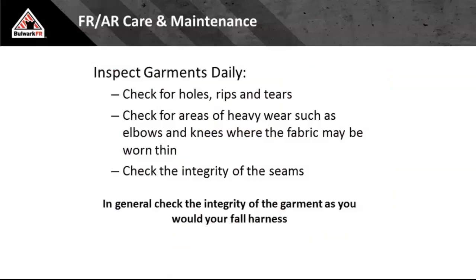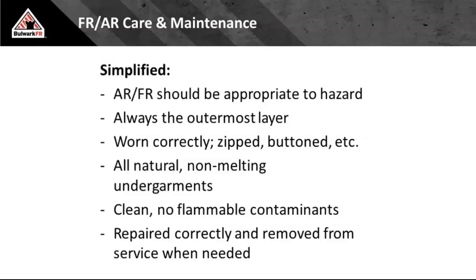So inspect your garments daily. Check for holes, rips, and tears. Check areas of heavy wear such as elbows, knees, where the fabric may be worn thin, and the integrity of the seams. Take the same mindset with your FR, AR clothing that you do with your fall protection. Take the same attitude you would with your hard hat. You don't allow hard hats with cracks and chips to go into service. You don't wear cracked, chipped safety glasses. You don't wear just one hearing protection because the other side's all messed up, the foam is all torn, chipped. So keep the same mentality that you have with all your other PPE when you're checking this. Don't put it in service if you are in doubt.